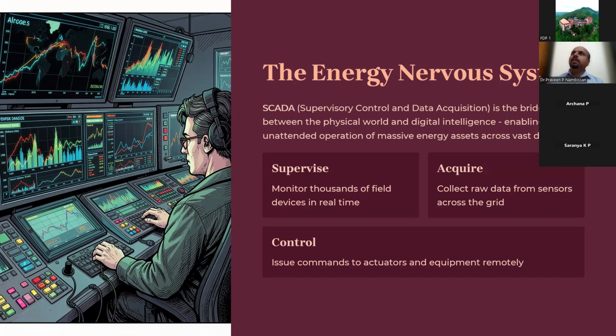That means controlling peripheral devices like actuators—for example, a control valve, whether electronic or pneumatic, has an actuator, often a box that opens or closes the valve based on signals. The basic current range is 4 to 20 milliamps, and pressure is about 3 to 15 psi, forming the control system actuator signaled from SCADA systems.